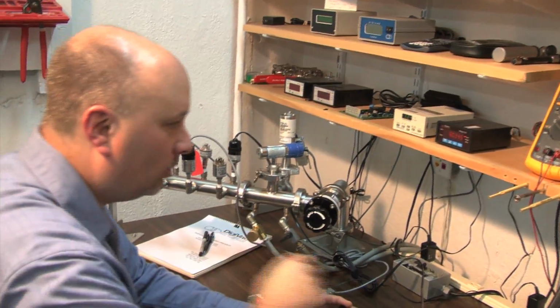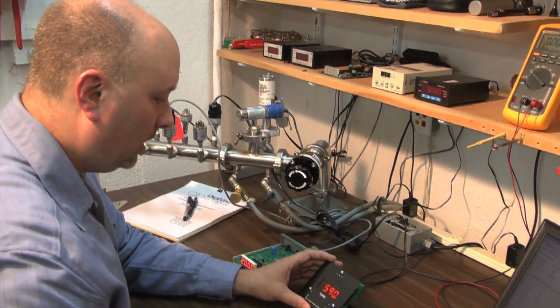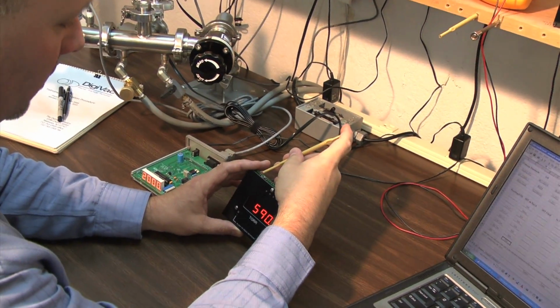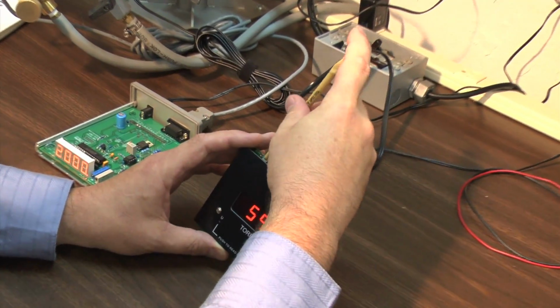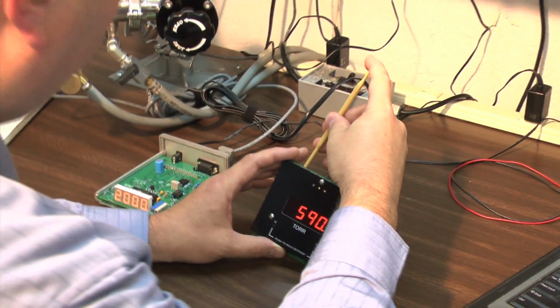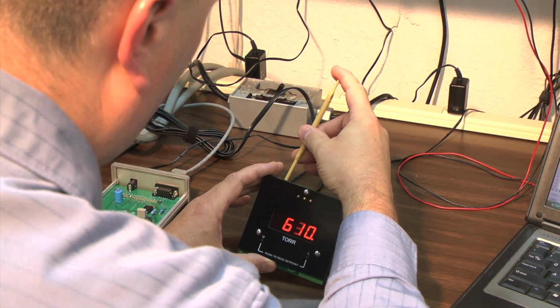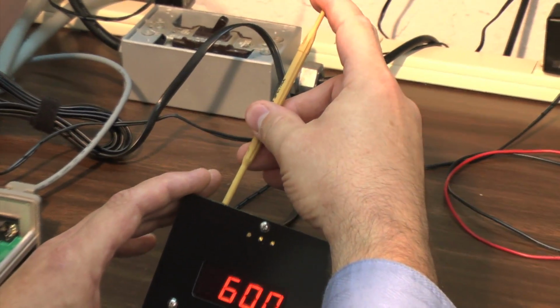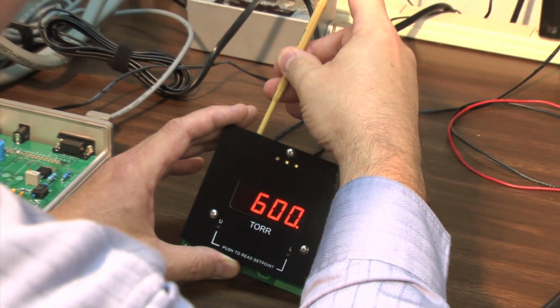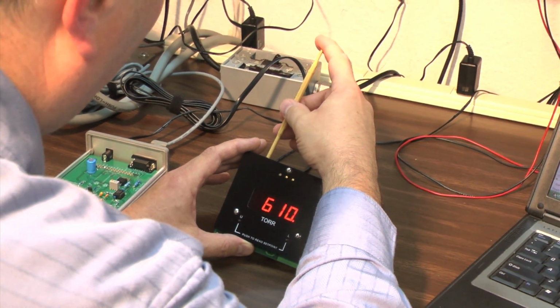603 torr, acceptable place to take a reading. Using the span adjustment on our 801W, we're going to increase the potentiometer clockwise so our 801W reads right on the threshold of 600 torr. Barometron reads 602, 801W reads 600. That's a good start.